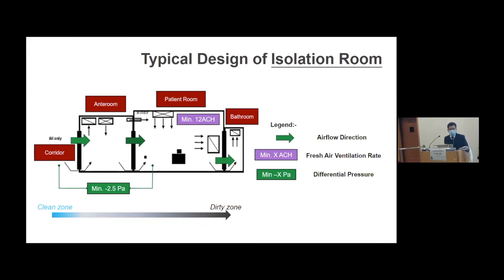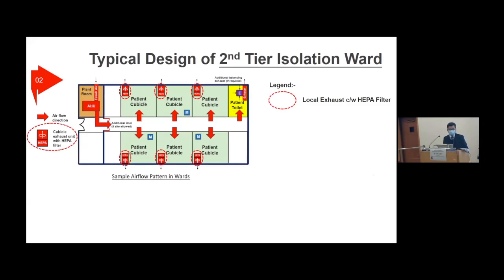In the early stage of the COVID-19 outbreak in Hong Kong, the Hospital Authority wished to enhance the handling capacity of COVID-19 patients in the public hospitals. So they came up with an idea to convert some of the general wards to so-called second-tier isolation wards. The design of the second-tier isolation ward is simply changing the airflow pattern of the ward. Fresh air flows into the ward through air handling units and will float into the patient cubicles. The dirty air in the patient cubicle will be extracted out from the patient cubicle to outdoor through HEPA purification units.